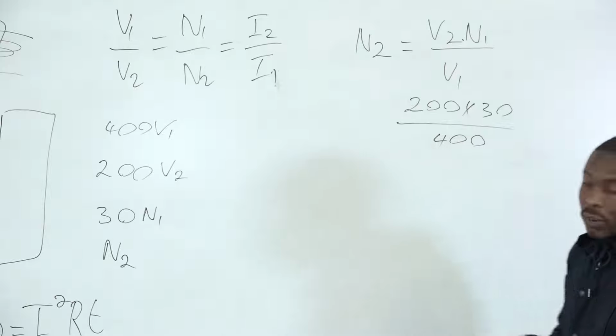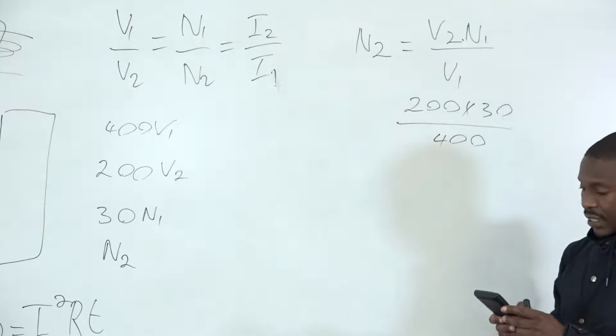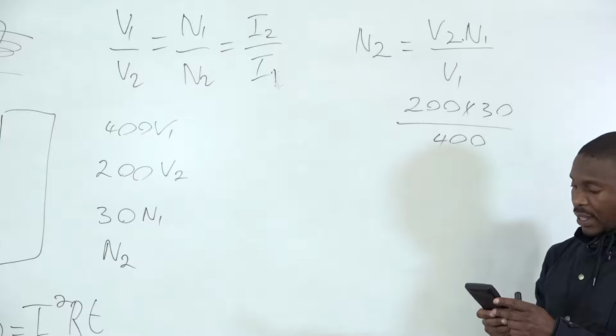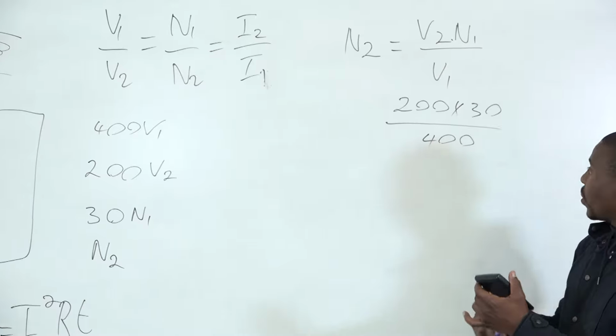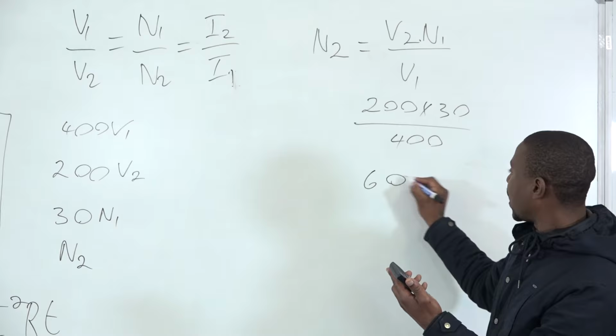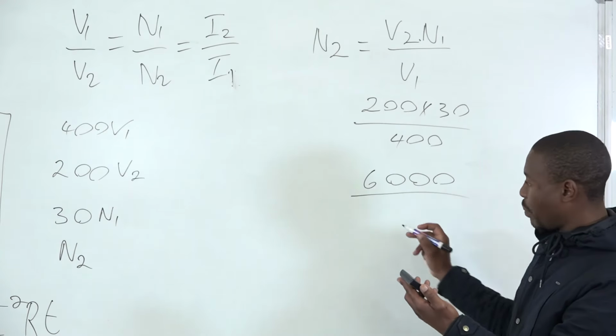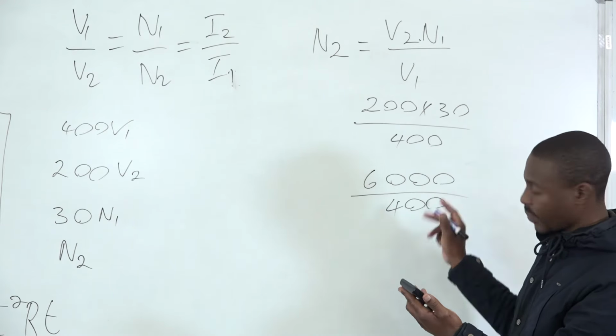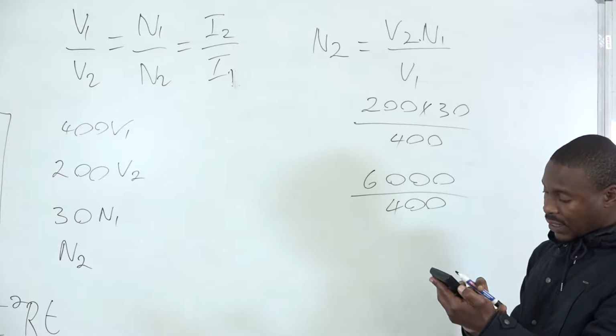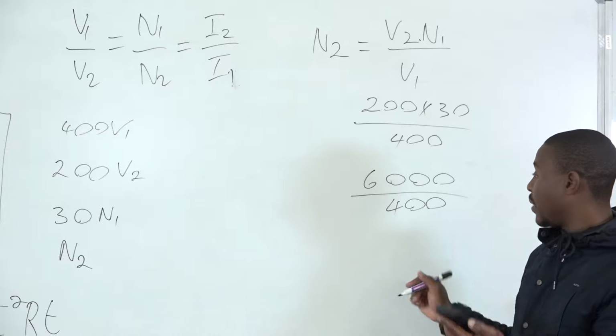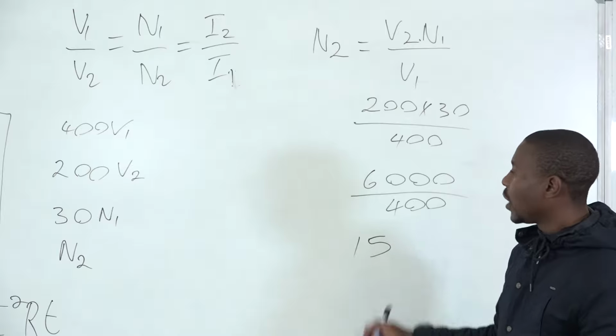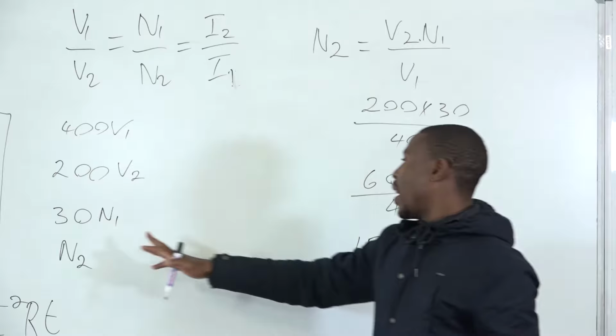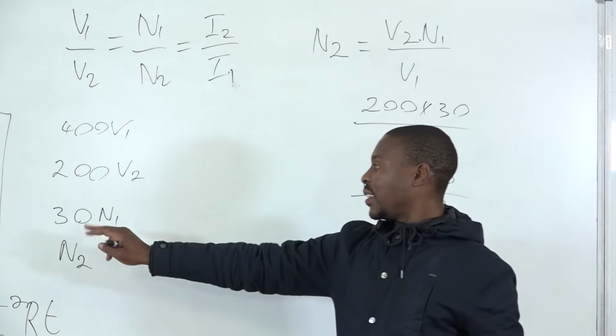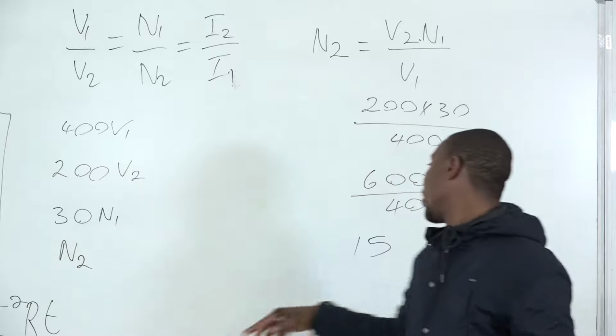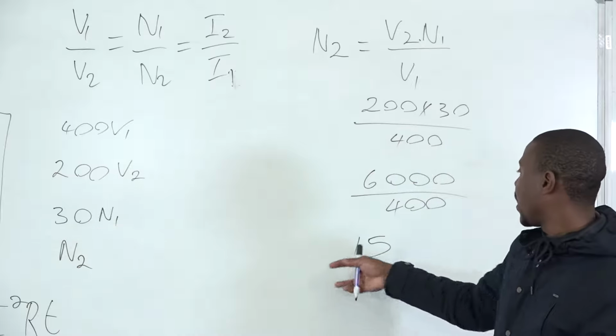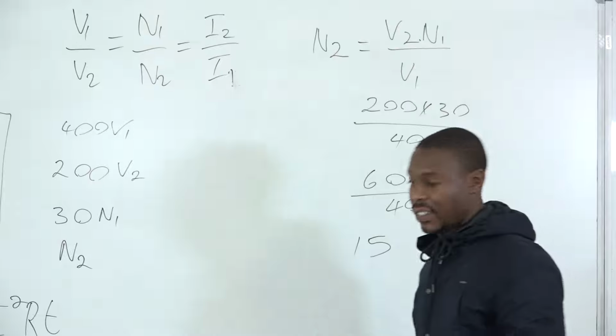From there, you take your calculator, you calculate 200 multiplied by 30, which will give you 6,000. Then you divide it by 400. Then 6,000 divided by 400 gives you 15. So it means when you are having this type of transformer, you're having 30 turns on the primary side. On the secondary side, you'll be having 15 turns.